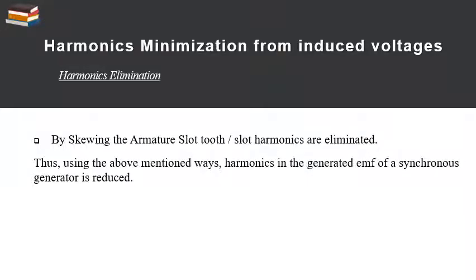By skewing the armature slot tooth, oblique slot harmonics are eliminated. स्क्वेइंग करना मतलब स्लॉट को सीधा डायरेक्शन में ला रख के थोड़ा कुछ एंगल पे टिल्ट करके स्लॉट को कट करना, उसको हम स्क्वेइंग बोलते हैं. Thus, using the above mentioned ways, harmonics in the generated EMF of the synchronous generator are reduced or minimized.